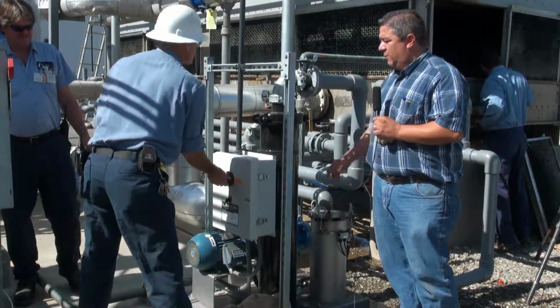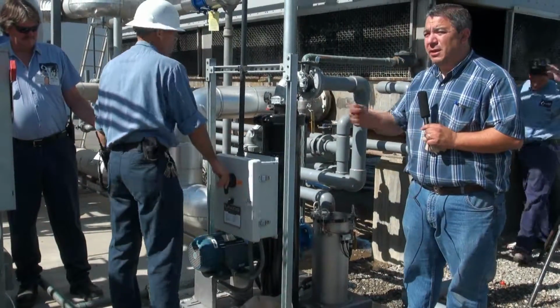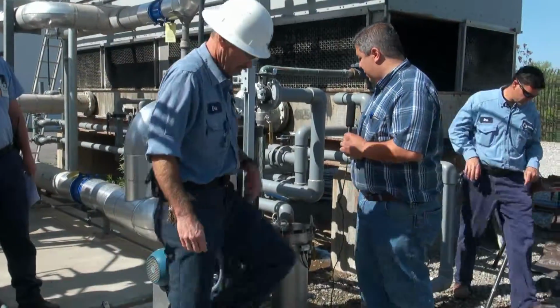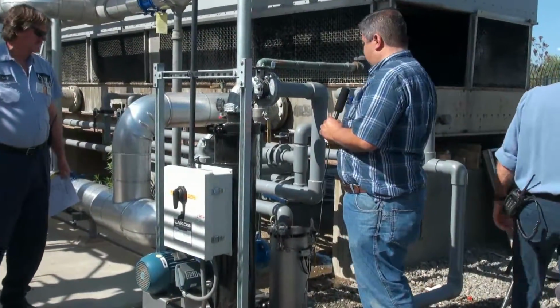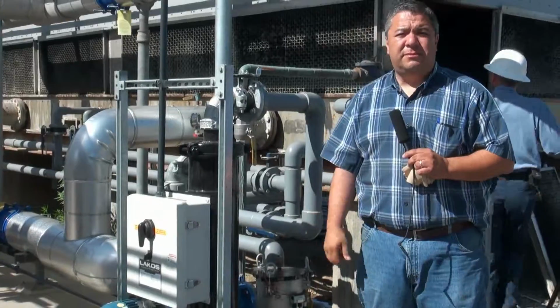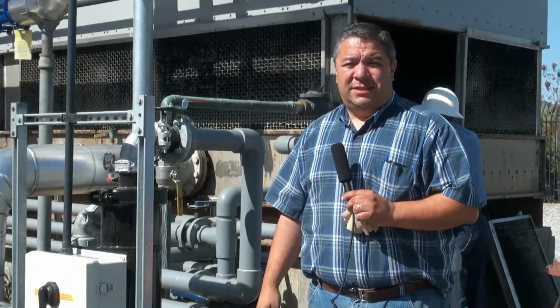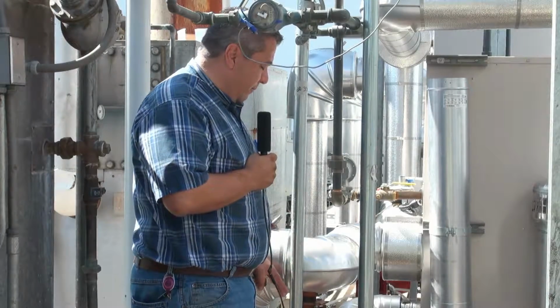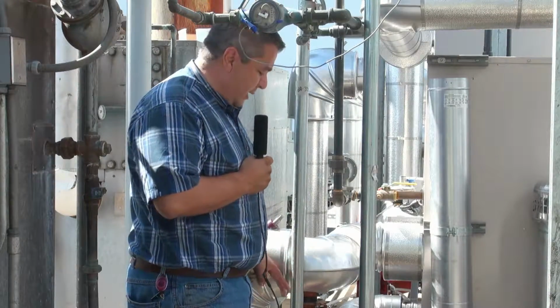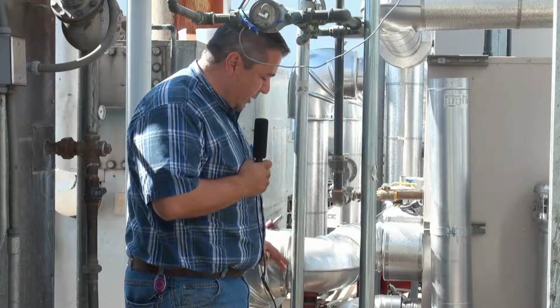And then also at the end of the year, open it up and do some vacuuming, make sure they're clean and everything. And then that's really all I got on them. Not a lot to them. These are simple single pumps. There's no VFDs on them. They run at one speed and that's it. They don't have to be lubricated. These are close coupled.